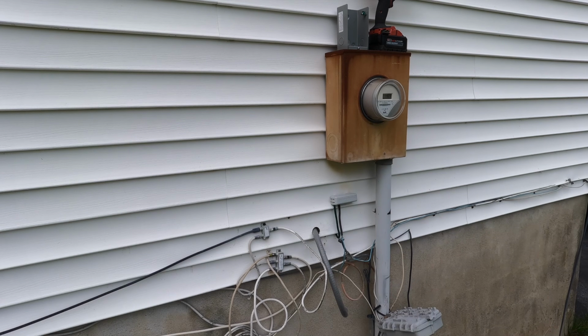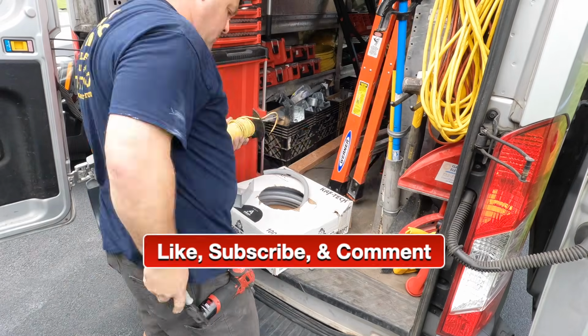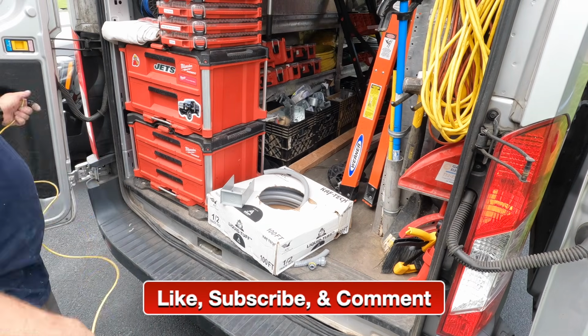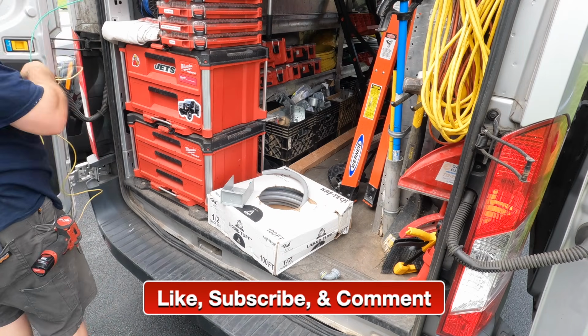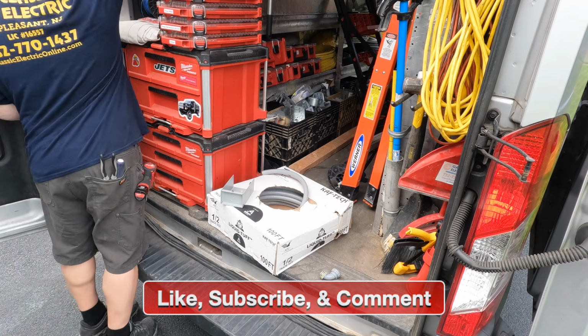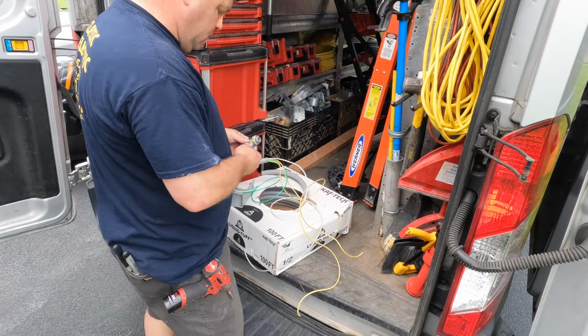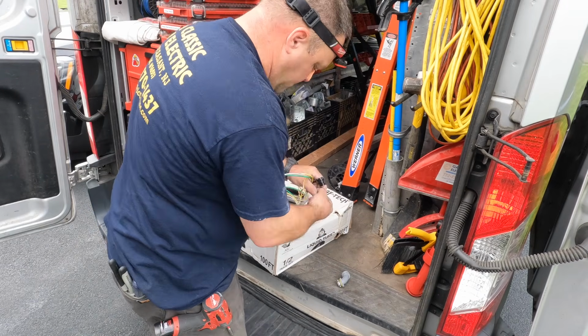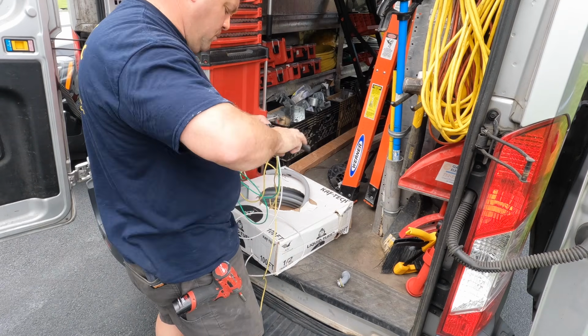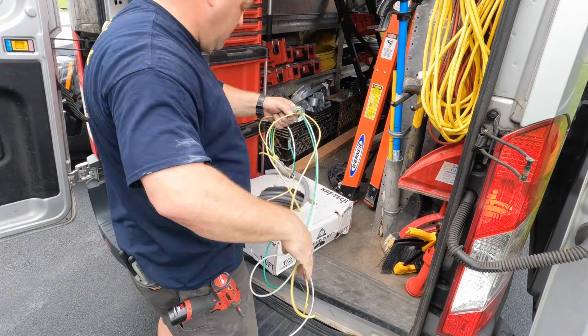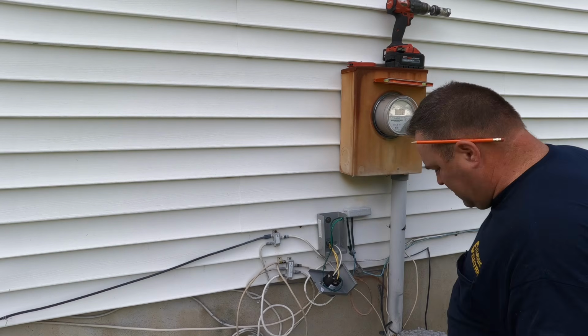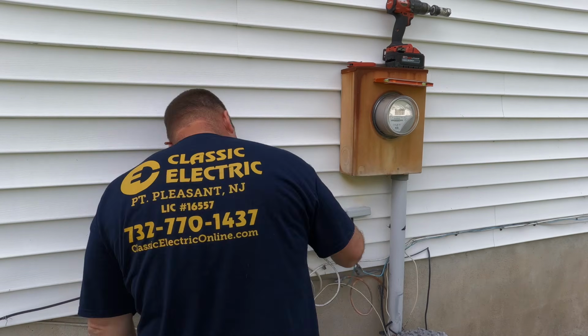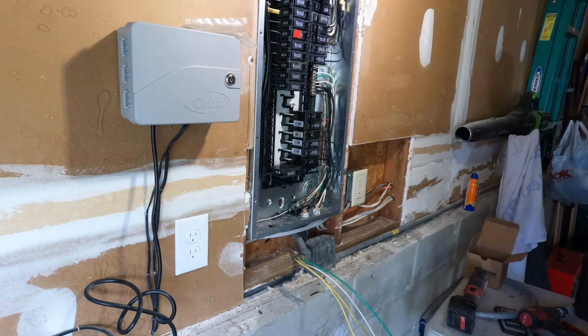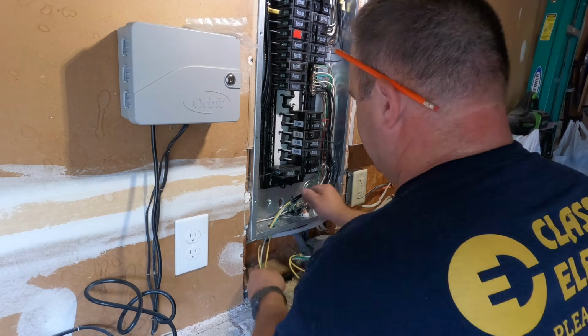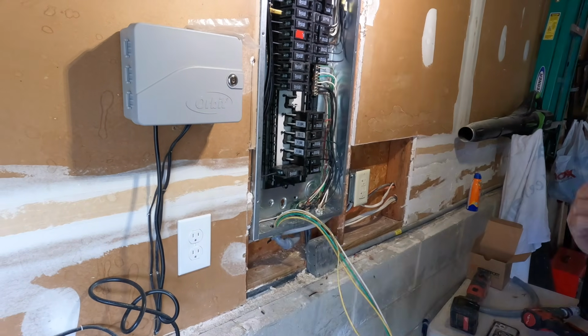So the next thing we did was we installed portable generator wiring, which consists of a 240 volt 30 amp circuit from the generator breaker that we installed inside the panel to the inlet box on the outside. We run number 10 AWG for all of our conductors. We've got 2 hots, a ground, and a neutral. And so 30 amps at 240 volts can provide 7,200 watts of power from your generator to your home. That's if you have a generator that size.